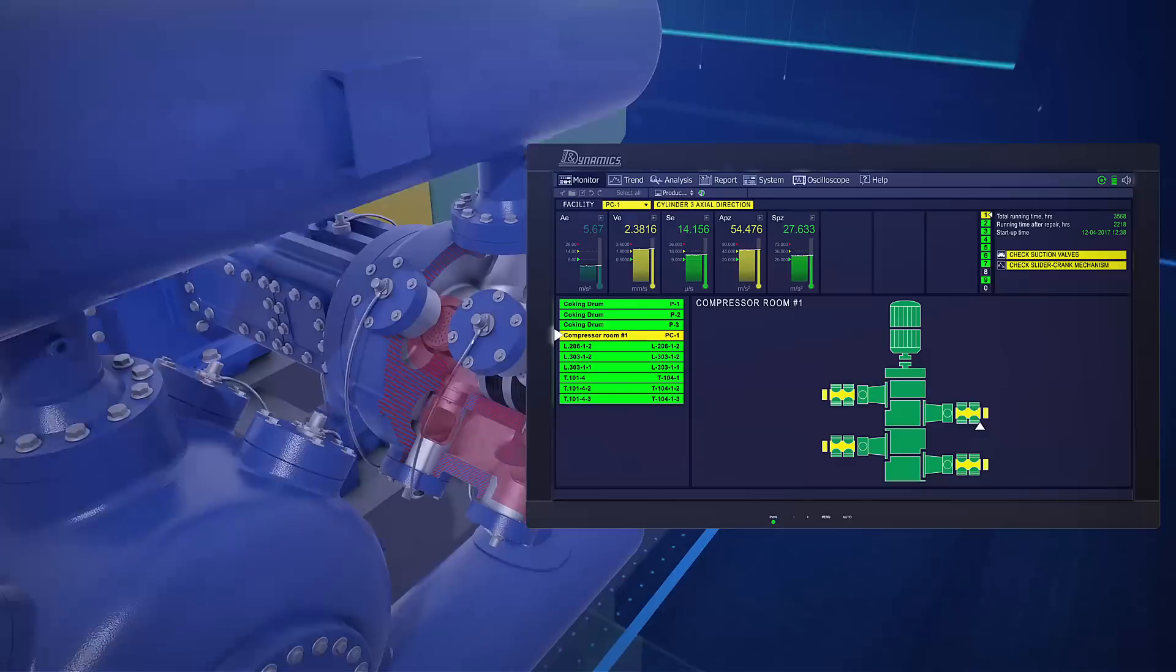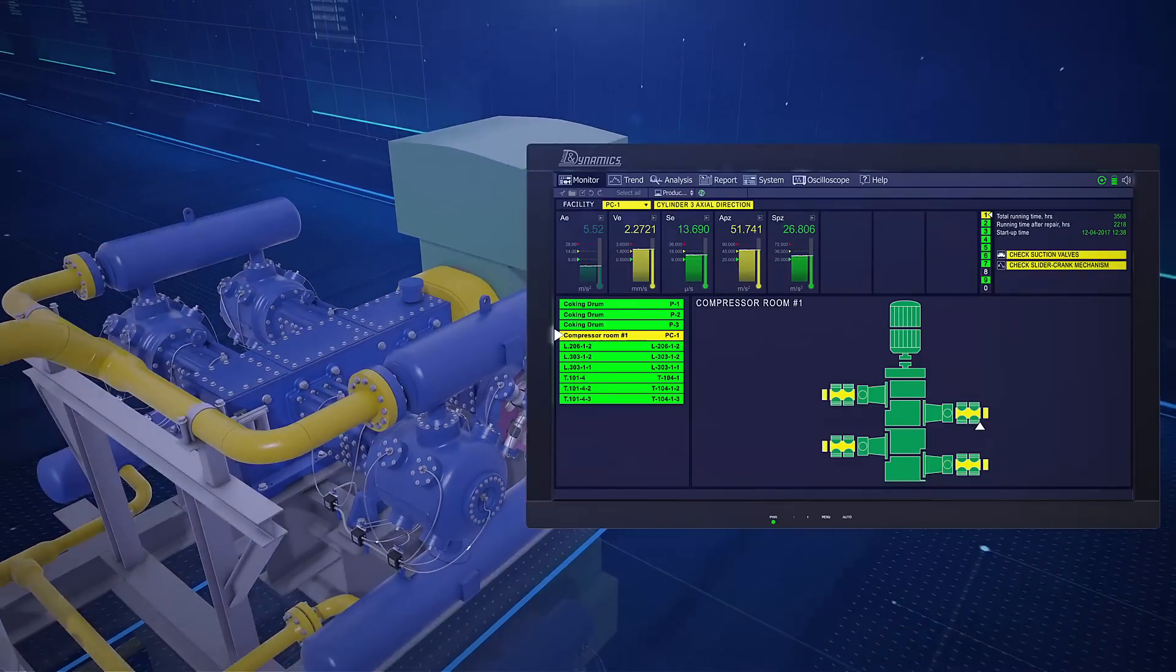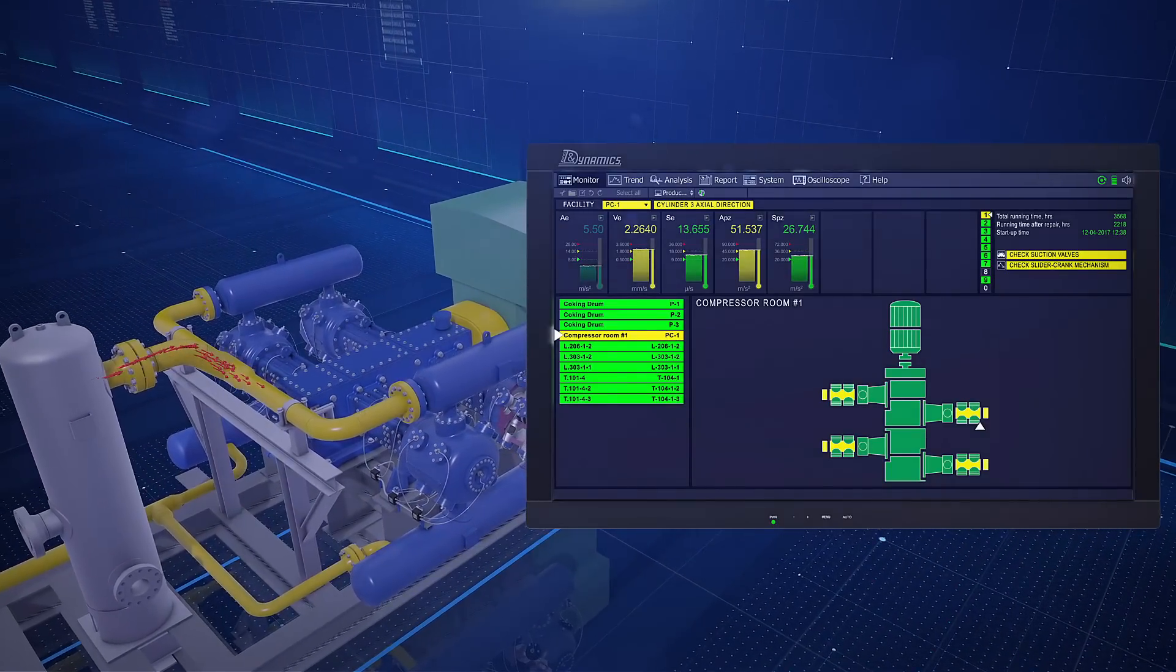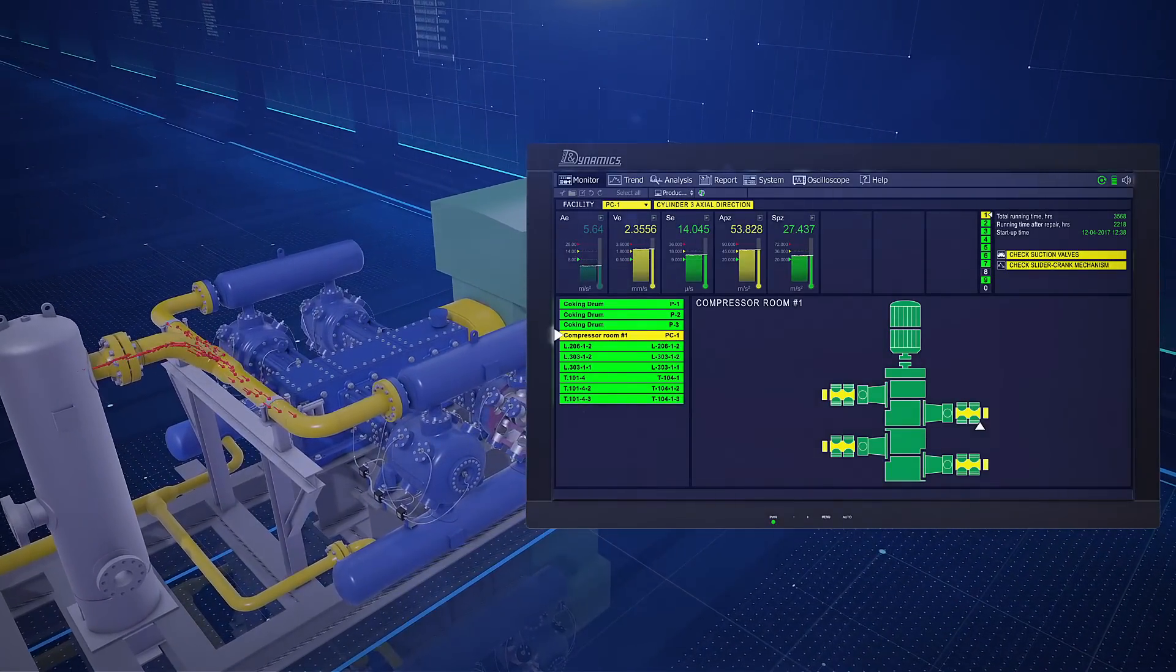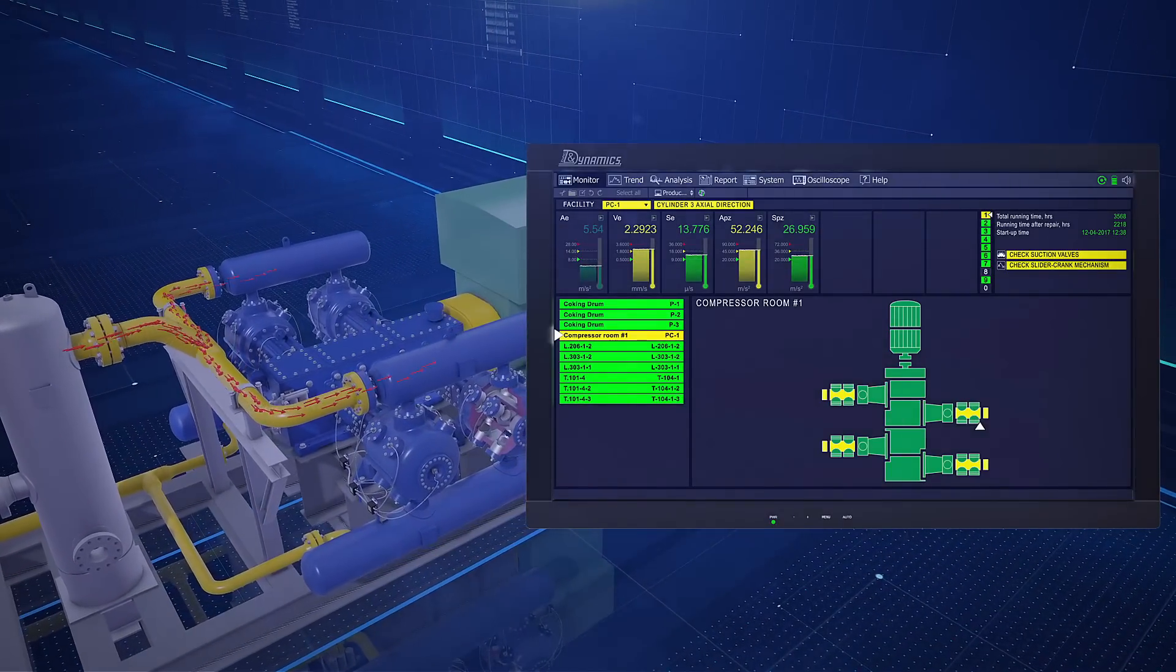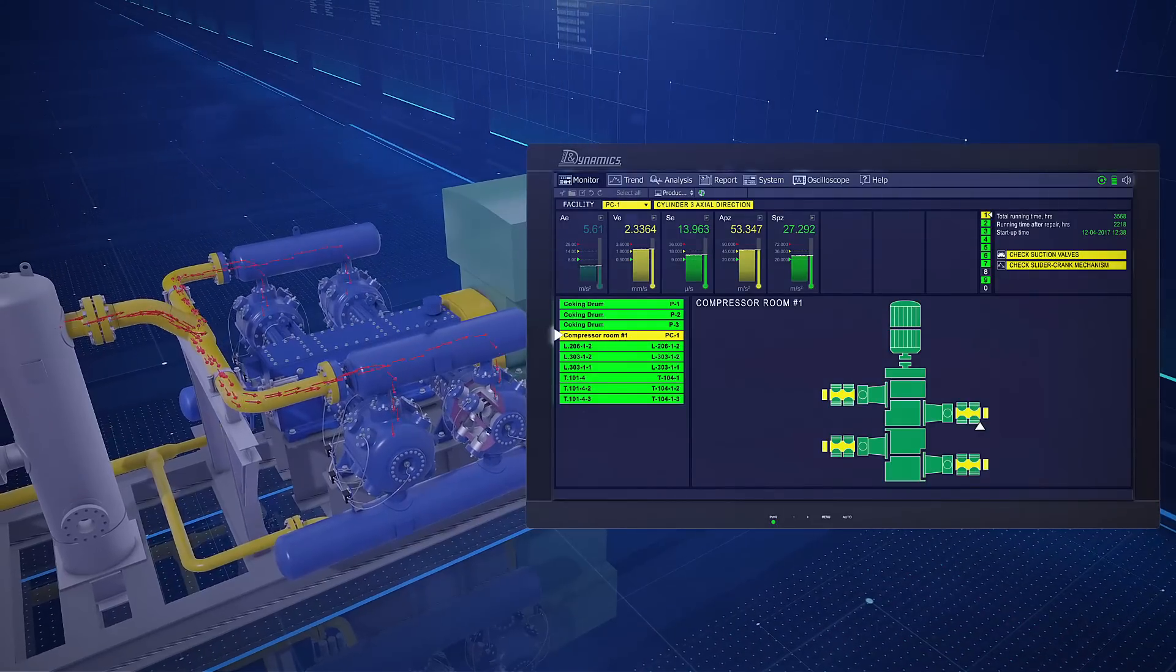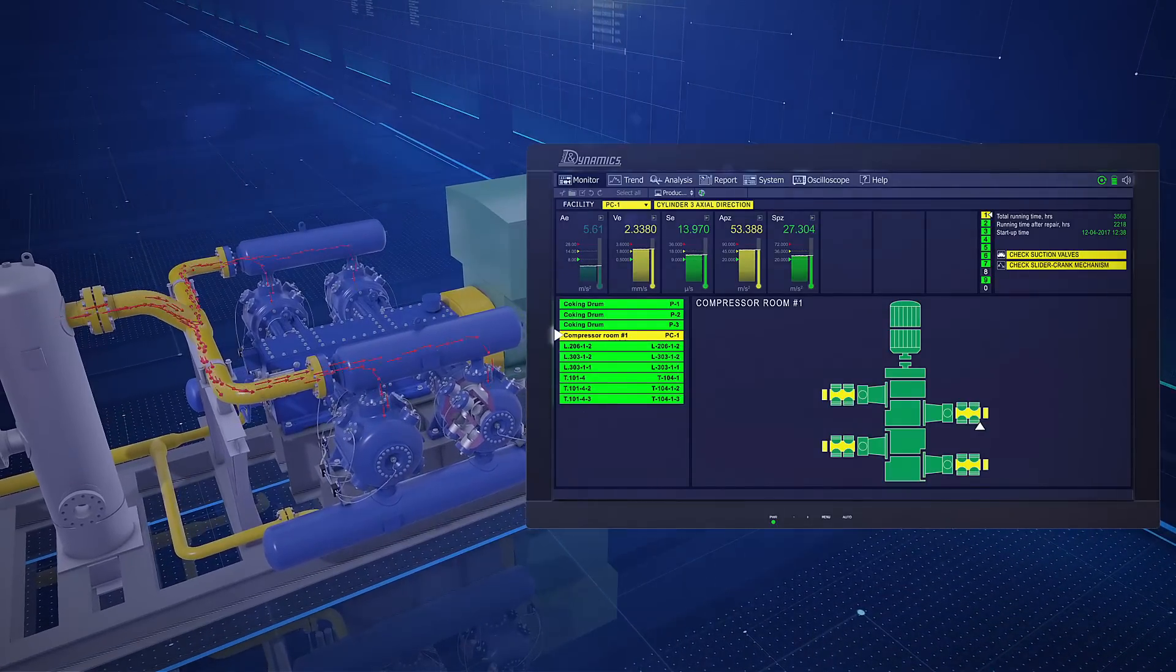Further investigation revealed that there was no filter between the compressor and it was dirty gas causing hydraulic shocks and valve deterioration, thus poor compressor reliability.